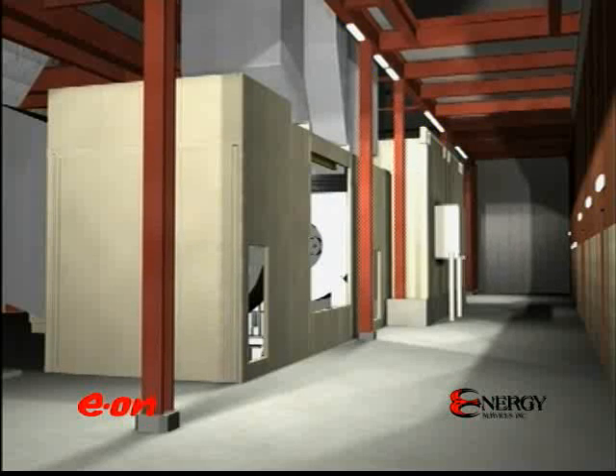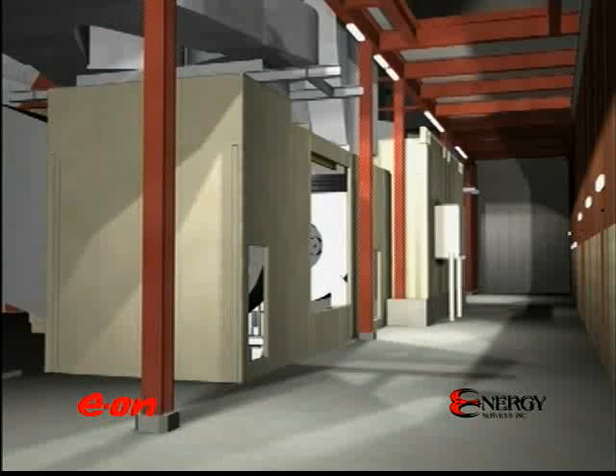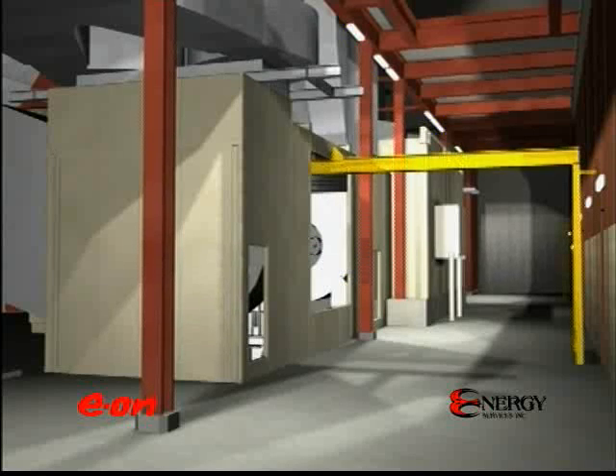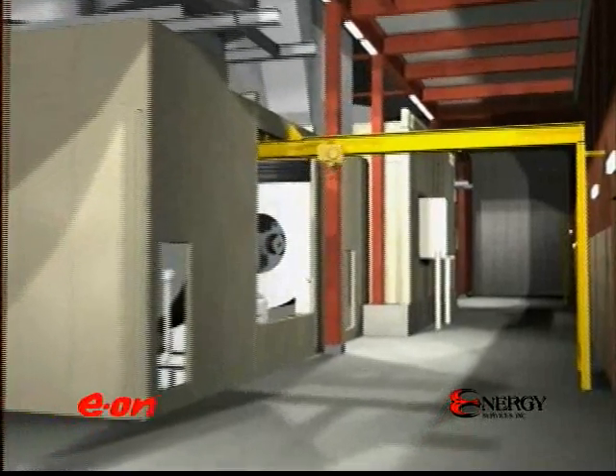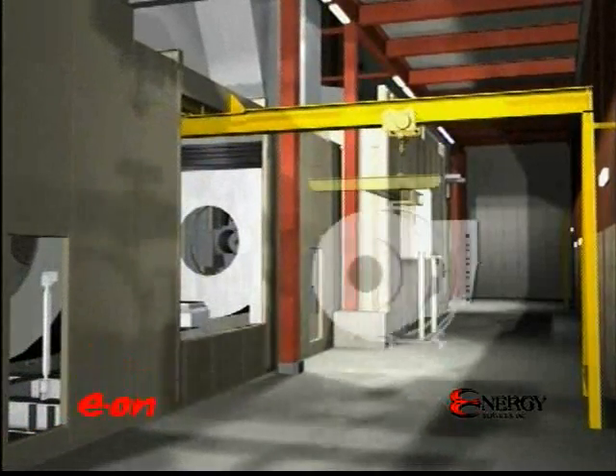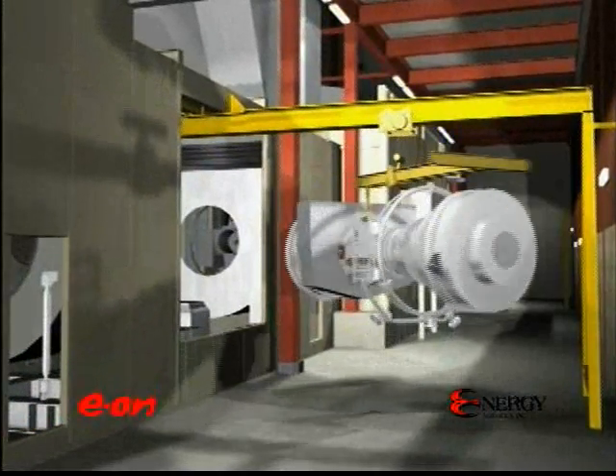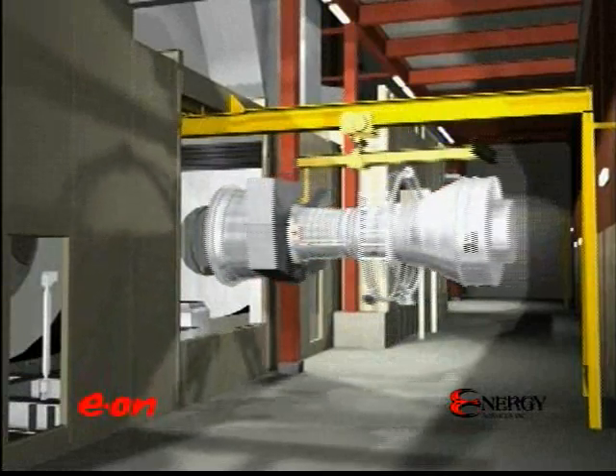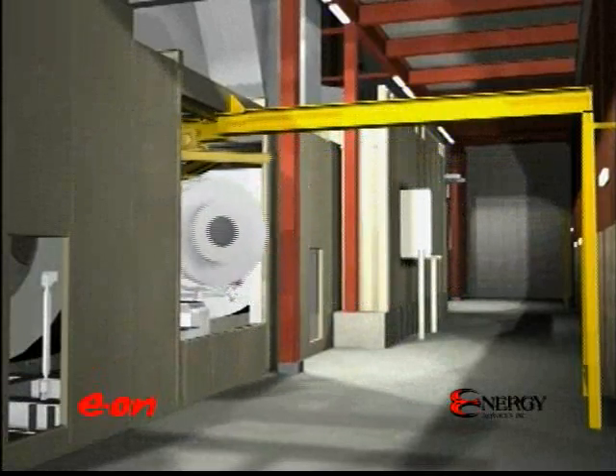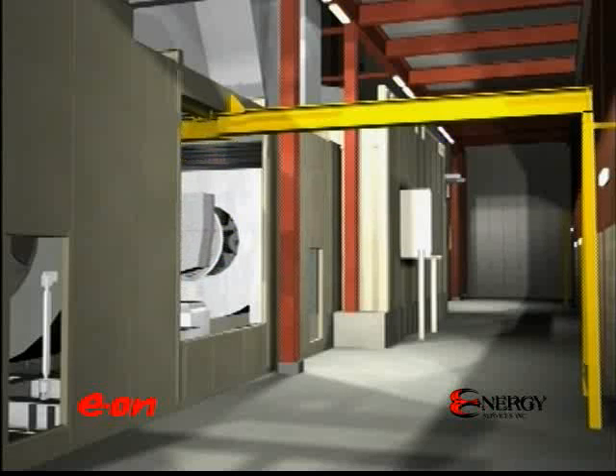The gas turbine enclosure cooling air exhaust fans and ductwork were added to complete the enclosure cooling air system. The engine removal beam and its supporting A-frame were then installed. This one removal beam is used for either engine, but each enclosure has its own A-frame permanently installed. Here we can see how the Unit 1 gas turbine, supported by the engine lift fixture, was moved into its enclosure. Both the Unit 1 and the Unit 2 gas turbines were installed in this manner, and both on the same day.